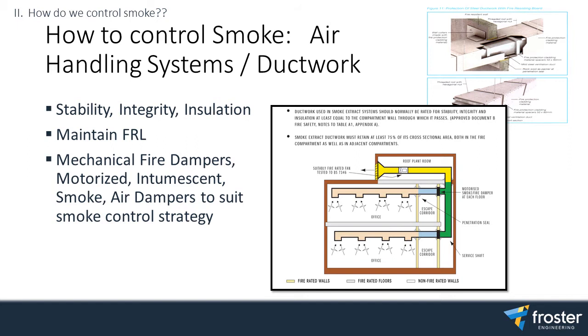exhaust. So it's our job to ensure that we size the ducts correctly in the first place to cater to the air quantity or the air volume. But also when we're on site inspecting, we want to make sure the integrity of that ductwork is proper. One key problem that we've seen a lot in the industry: if you have a duct, see these supports here? Say that's just a sheet metal duct right here. A few more slides will have a fire damper. If there's a fire damper fixed directly to that with a hard connection to a flange, that's technically non-compliant.